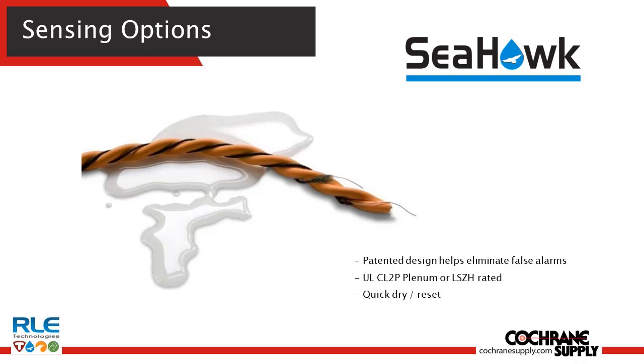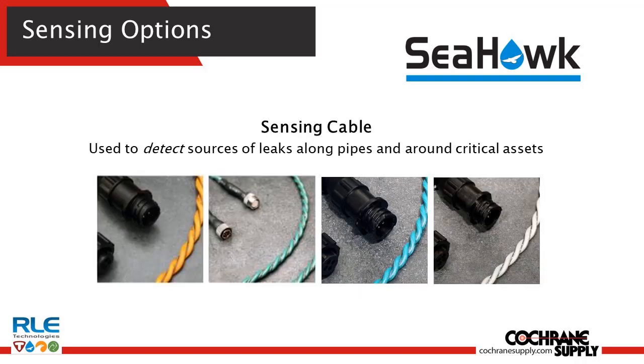The sensing cables are a patented design that helps eliminate false alarms. There's a thread around the two wires that wrap around the orange cable or other colors based on the different designs that are available. And they're plenum rated CL2P as well as a quick dry reset. So the standard cable is an orange conductive cable. The green cable is a chemical cable, still looking for a conductive fluid, though they are much more resistant to harsh environments. And then our rodent resistant and zero halogen cables are also available based on the different environments that you may be putting them in.